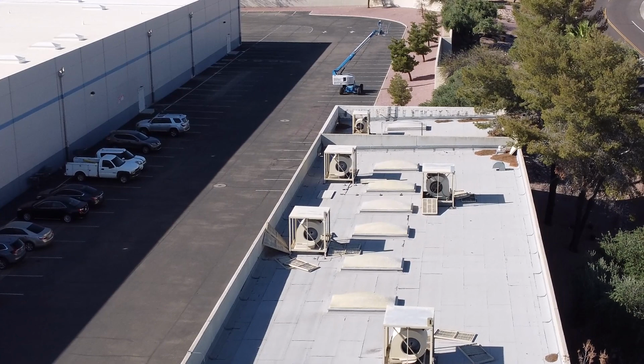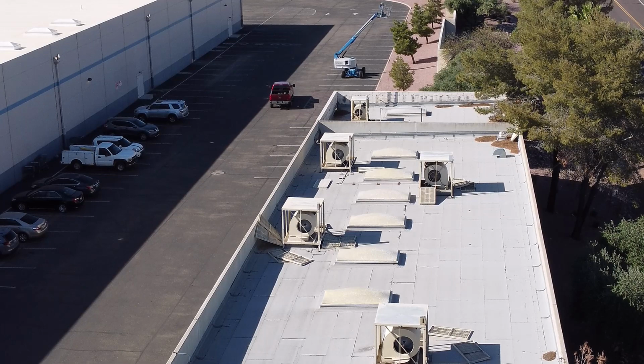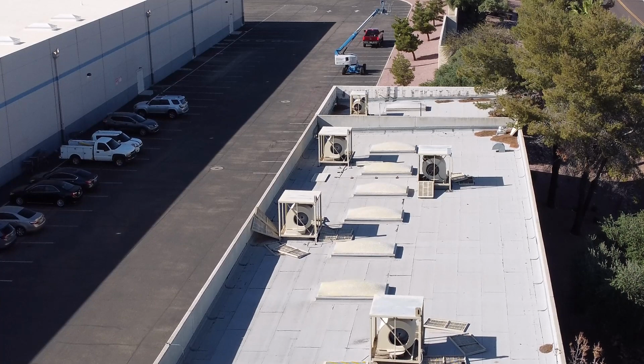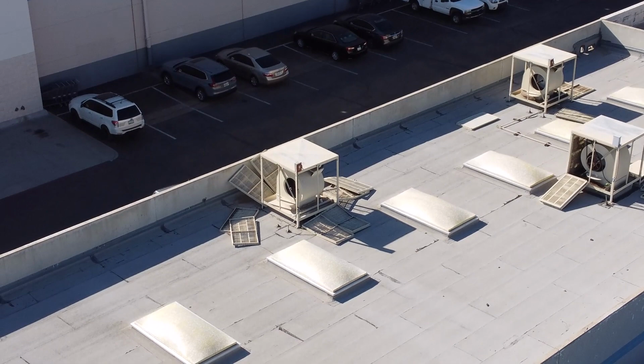Yep, so much for that. Oh, there's some right there. These are what I call the eight-sided coolers. It's four sides, but it's got two panels per side that you have to just get those stupid wire hooks out to get the retainer brackets off. And then if they don't change their pads every year, those things would turn into concrete, basically, with all the hardened minerals. You have to pound them with a hammer or whatnot.